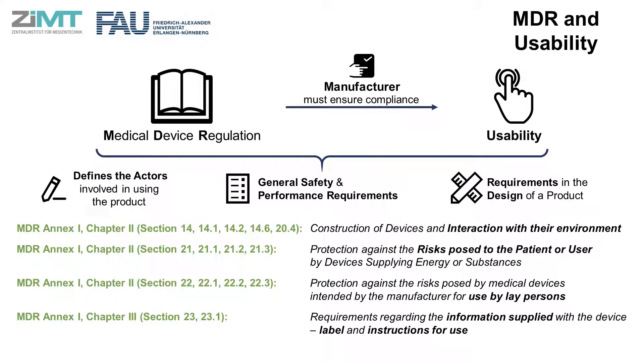Moving on to the usability requirements regarding the design and manufacture of a product, Annex 1, Chapter 2 of the MDR states that particular attention must be paid to the construction of devices and interaction with their environment, such as protection against the risks posed to the patient or user by devices supplying energy or substances, and also protection against the risks posed by medical devices intended by the manufacturer for use by laypersons. Annex 1, Chapter 3 of the MDR then speaks to the requirements regarding the information supplied with the device, and describes how labels and instructions for use should be written. Please note, relevant sections are written in brackets.